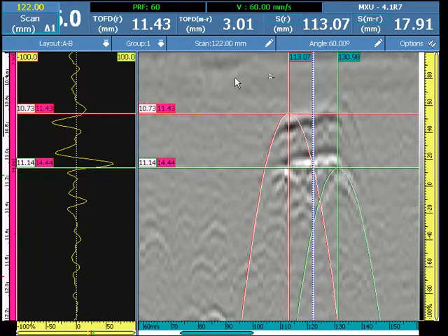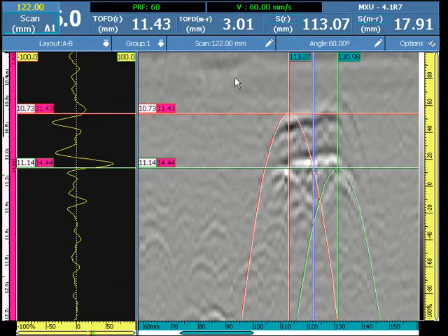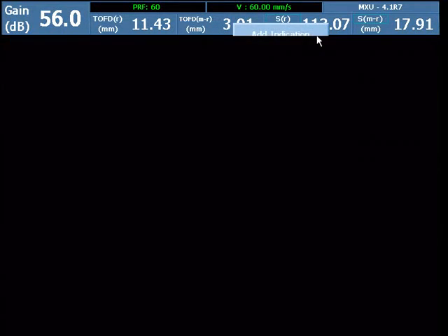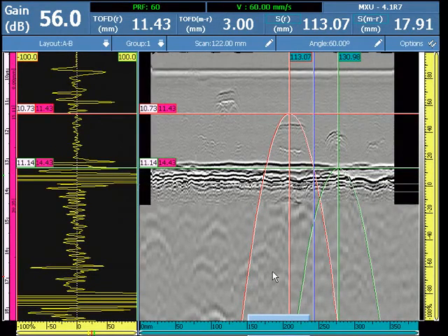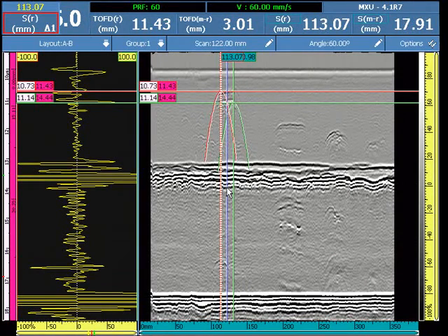Once the zoom is appropriate and the cursors have all been placed, the indication can be added to the indication table — which will appear on the report — by a touch and hold in the readings area and selecting add indication. A screenshot of the data is recorded with the indication table entry. We can then zoom out and continue to the next flaw.